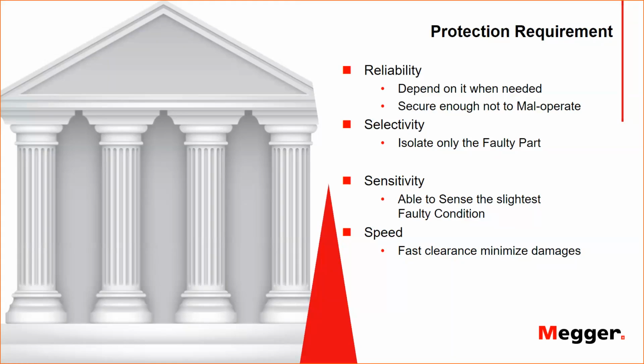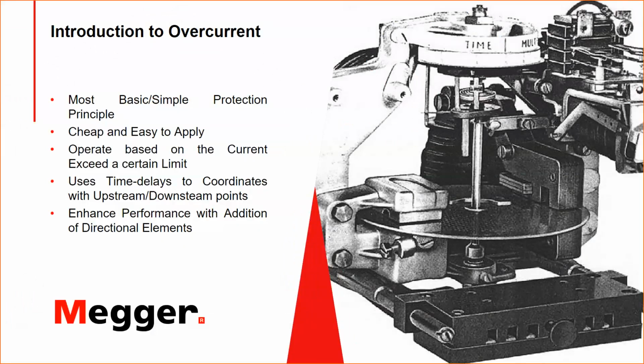So the first protection principle that most people deal with, or most protection circuits are dealing with, is overcurrent protection. Overcurrent protection is the most basic and simple, and it's the cheapest and easiest to apply. It's very simple. Whenever the current, depending on which phase or loop you are measuring, exceeds a set value or a certain limit that you put, an operation of that protection will start. This operation could be time delayed to achieve coordination or selectivity, or could be instantaneous to achieve speed. This really depends on the type of power system that you have.